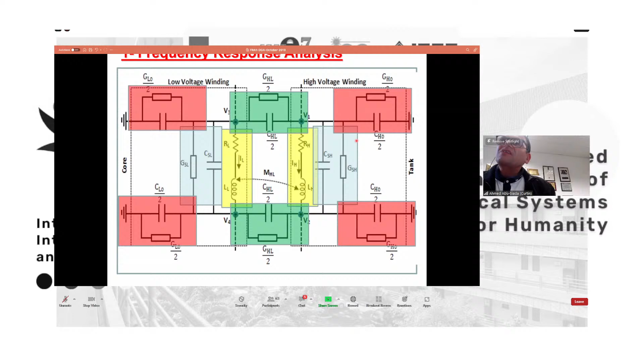So the technique, the measurement itself, is very easy and simple. Anyone can do it. But you have to take the transformer out of service because you have to scan the transformer over the right frequency range. You can't perform the test at the power frequency, 50 or 60 hertz. You need to detect inductive components, which can be detected at low frequency, as well as capacitive components, XC equals 1 over omega C, which would be detected at very high frequency. So the typical frequency range for the test would be from very low frequency, like 10 hertz, to very high frequency, 2 megahertz. And that's why you have to take your transformer out of service, because you need to inject variable frequency into the transformer.